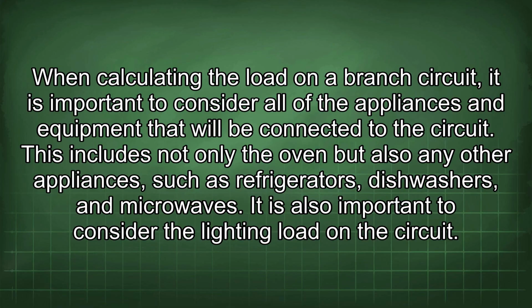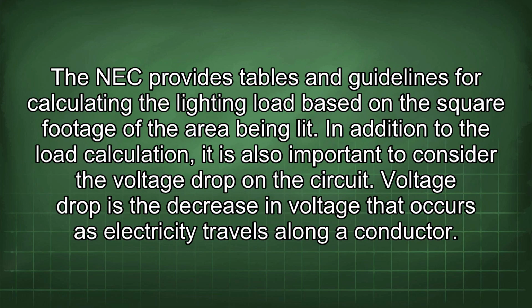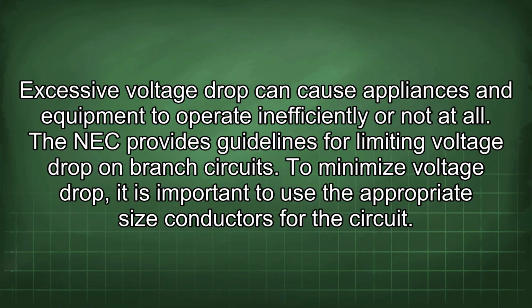This includes not only the oven but also any other appliances, such as refrigerators, dishwashers, and microwaves. It is also important to consider the lighting load on the circuit. The NEC provides tables and guidelines for calculating the lighting load based on the square footage of the area being lit. In addition to the load calculation, it is also important to consider the voltage drop on the circuit. Voltage drop is a decrease in voltage that occurs as electricity travels along a conductor. Excessive voltage drop can cause appliances and equipment to operate inefficiently or not at all. The NEC provides guidelines for limiting voltage drop on branch circuits.